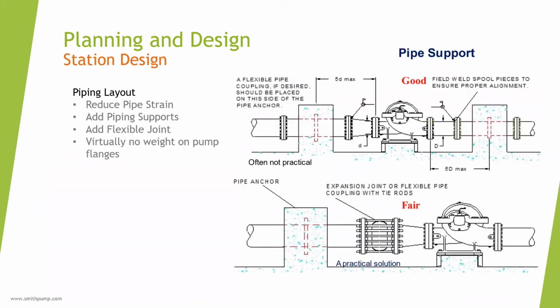So here's some improved piping support layouts. The bottom shows improved pipe support, but more support should be added to reduce the flange loading. It has a flexible coupling to reduce pipe strain from misalignment, which is good.